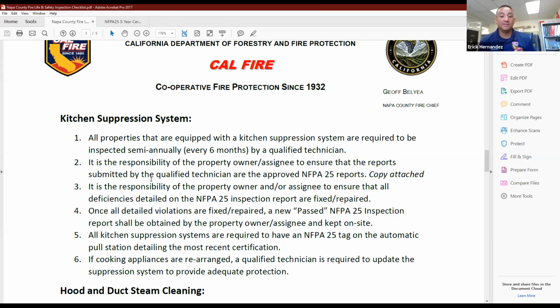One of the things that I'm finding is lots of times when I'm asking for these documents for when was the last time that your hood system was cleaned, some of these restaurants are telling me, well, we clean the filters every night, and so we're good. Just to make sure, the filters is just a small component of the hood system. Typically, most fires occur in the plenum because of buildup and not being properly maintained. So that's something to look for as well.